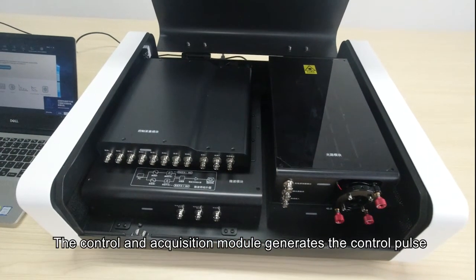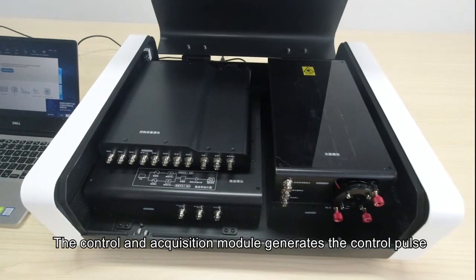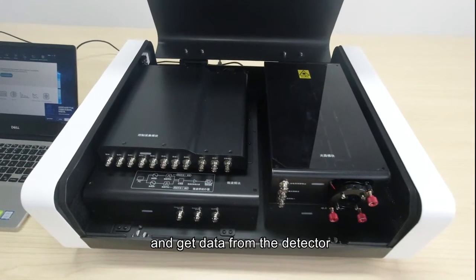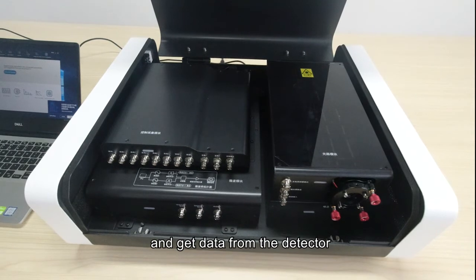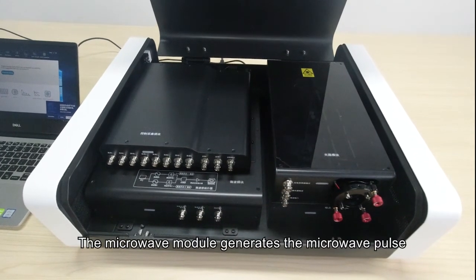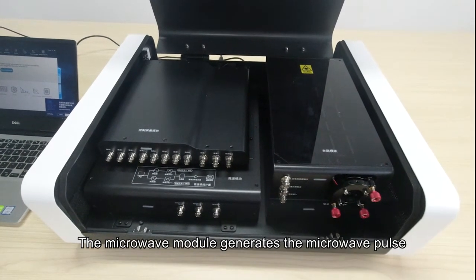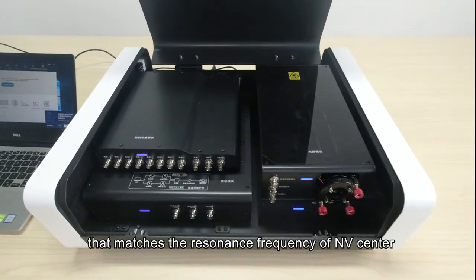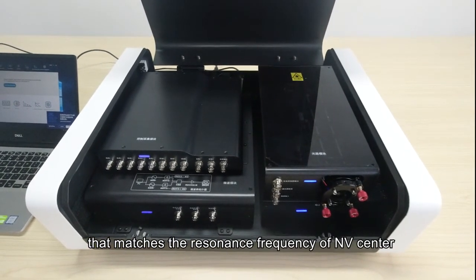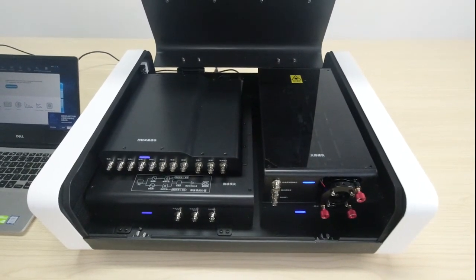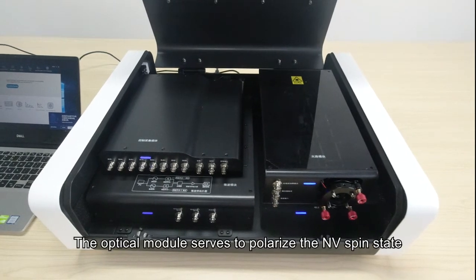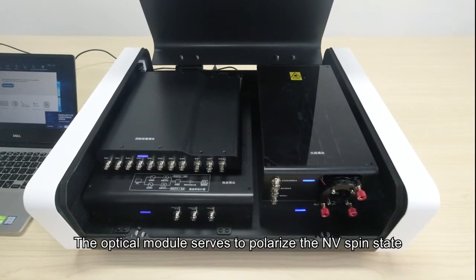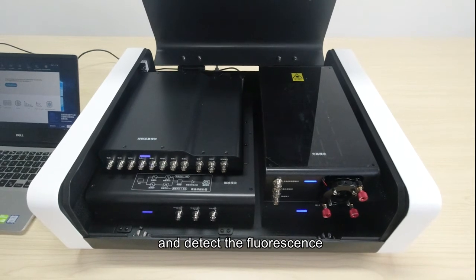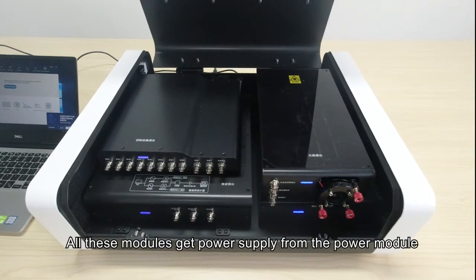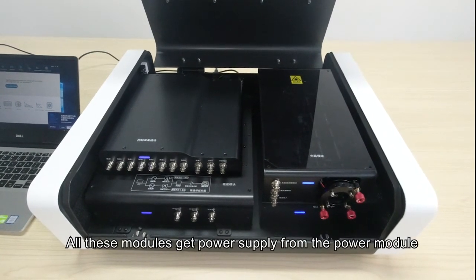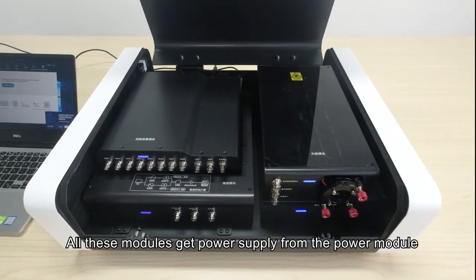The Control and Acquisition Module generates the control pulse and gets data from the detector. The Microwave Module generates the microwave pulse that matches the resonance frequency of an NV center. The Optical Module serves to polarize the NV spin state and detect the fluorescence. All these modules get power supply from the Power Module.